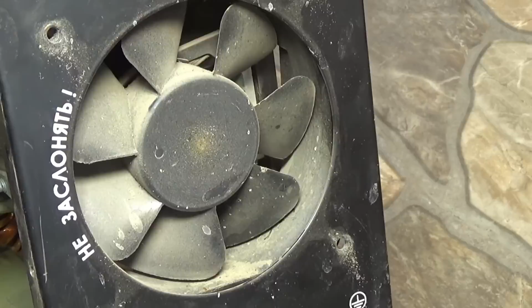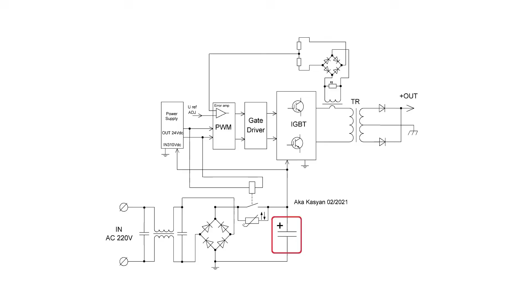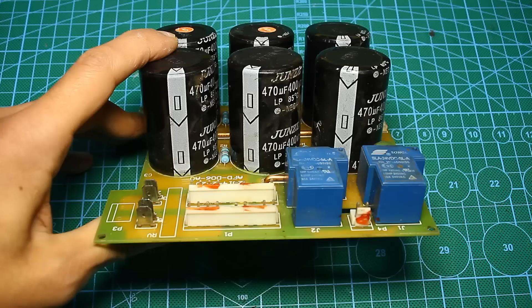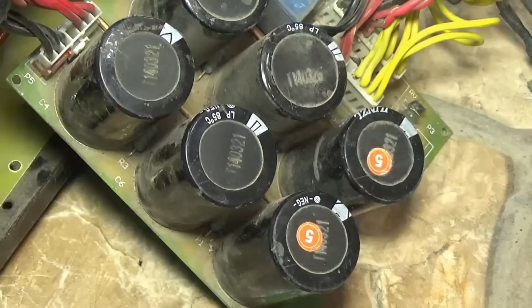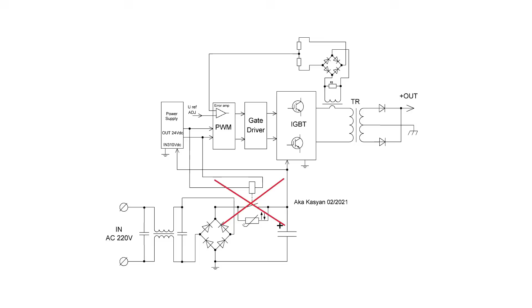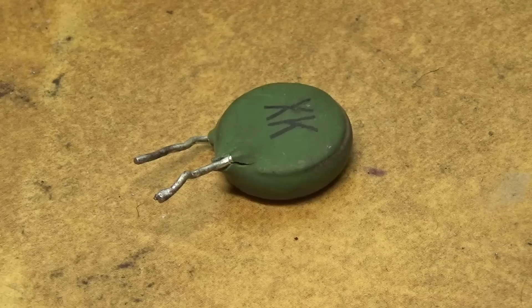and control system. Network power is rectified and charges the input capacitors through a current-limiting resistor. The resistor, or thermistor, connected in parallel to the relay contacts, is necessary to limit the charging current of the capacitors at the moment the source is connected to the network. By its nature, a capacitor is a capacitive load, and its charging current is enormous. And considering the number of capacitors in this inverter, if a soft start is excluded, and the capacitors are charged directly, it will trip the circuit breakers and most likely burn out the input rectifiers. The resistor will limit the charging current, and the capacitors will charge to a certain voltage smoothly.